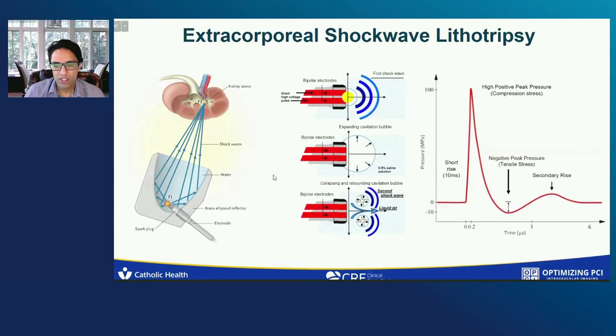To really understand the mechanism of action of shock wave, it's based on extracorporeal shock wave lithotripsy used for kidney stones. The way this works is basically a spark plug, which has two electrodes, creates a spark between the two electrodes. And in a parabolic fashion, it concentrates and focuses the energy. It's a little bit like your car headlights — there's a concave parabolic mirror inside the light that takes all the reflection and concentrates it so you get a straight beam rather than spreading the light everywhere.